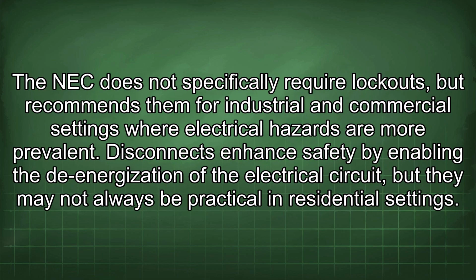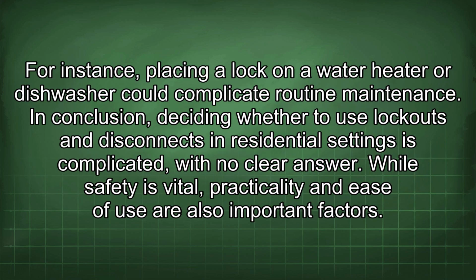The NEC does not specifically require lockouts, but recommends them for industrial and commercial settings where electrical hazards are more prevalent. Disconnects enhance safety by enabling the de-energization of the electrical circuit, but they may not always be practical in residential settings. For instance, placing a lock on a water heater or dishwasher could complicate routine maintenance.